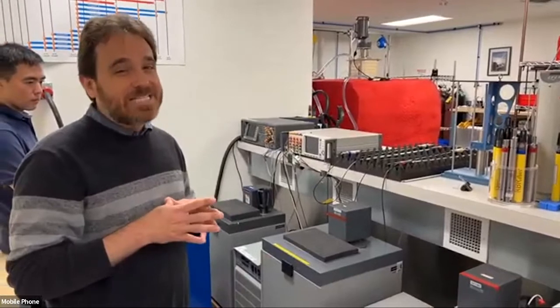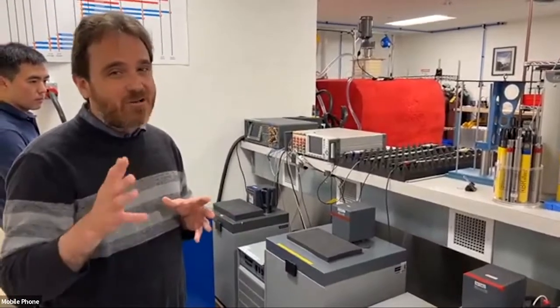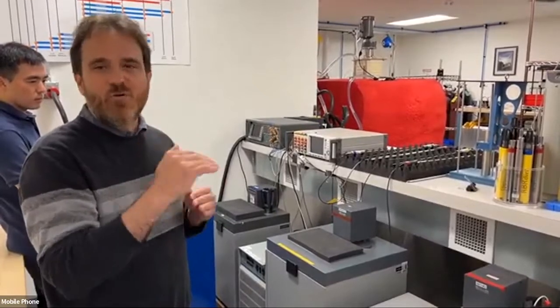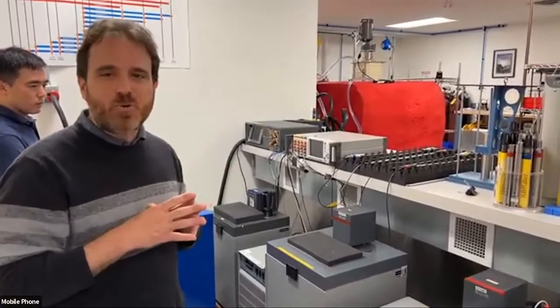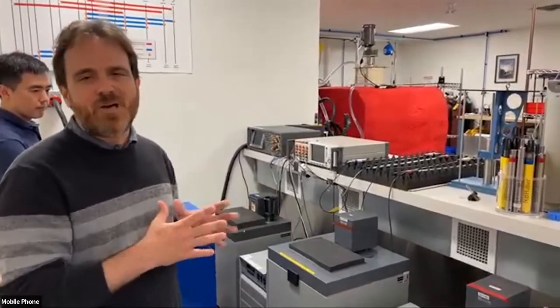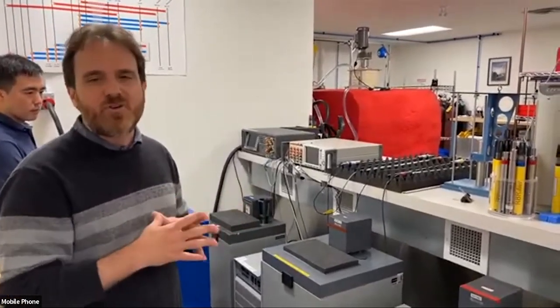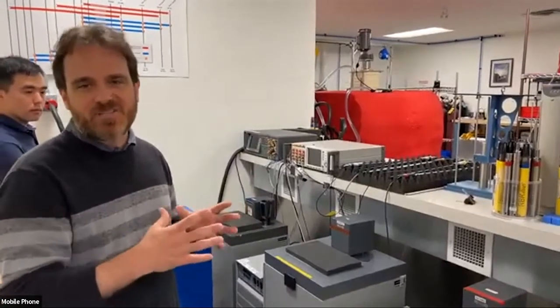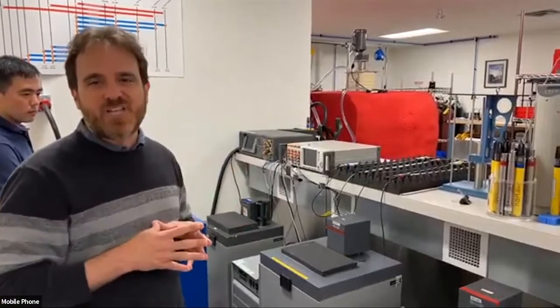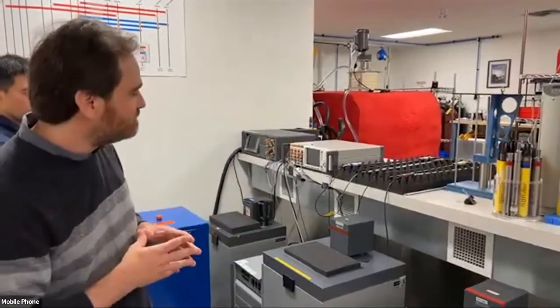The cycle typically takes around 10 to 12 hours. We do a 1-hour plateau for each of those temperature points, which is enough for equilibrium and stabilization time for both the instrument under test as well as our reference standard, which I will talk about now.